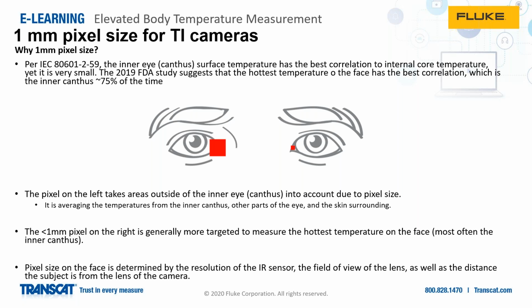The pixel size, as we talked about, is determined by the resolution of your IR sensor, the field of view of the lens, as well as the distance the subject is standing away. And typically these systems will specify how far away you have to be to try and achieve these specifications.